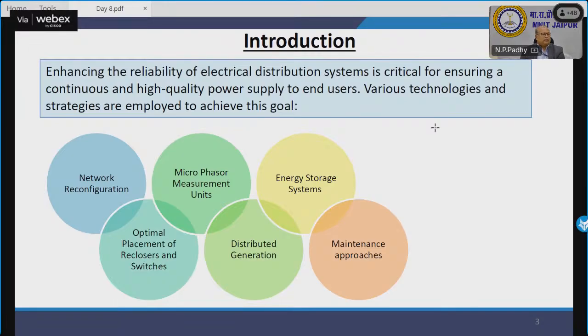Third is distributed generation. If you put distributed generation, why will reliability increase? Because there is no single point of failure. If the main grid fails, if the main generator fails, if the transformer fails, still the distributed generator placed at the low voltage network can cater to some of the loads. So with distributed generation, 100% failure is next to impossible.